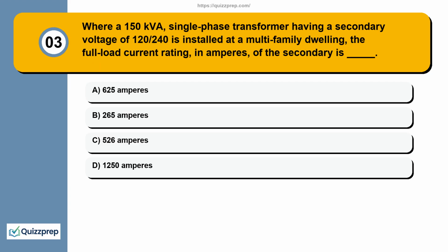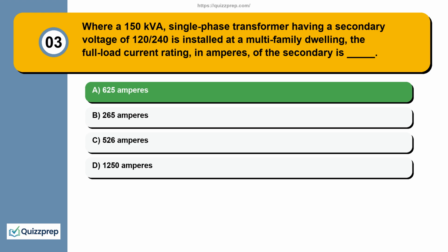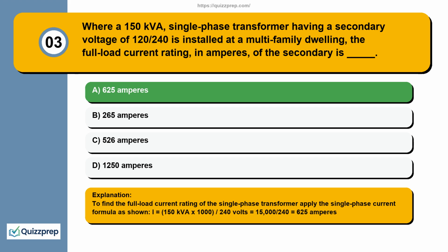Question 3. Where a 150 kVA, single-phase transformer having a secondary voltage of 120/240 is installed at a multi-family dwelling, the full load current rating, in amperes, of the secondary is 625 amperes, 265 amperes, 526 amperes, 1250 amperes. To find the full load current rating of the single-phase transformer, apply the single-phase current formula as shown. I equals 150 kVA x 1000/240 volts equals 150,000/240 equals 625 amperes.